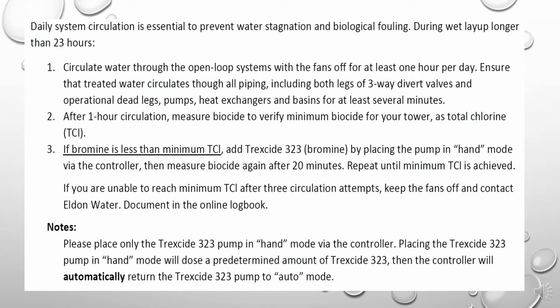So we want to make sure that we are circulating through our system every day and we are measuring our biocide for our tower. We want to circulate water through the entire system with our fans off for at least 1 hour per day. Ensure that treated water circulates through all of our piping, including both legs of three-way divert valves if you have it, and operational dead legs, pumps, heat exchangers, basins for at least several minutes.